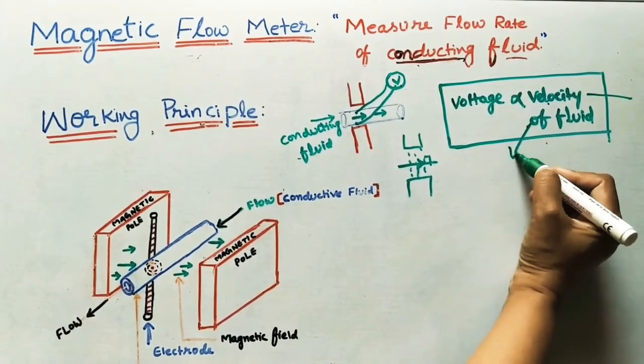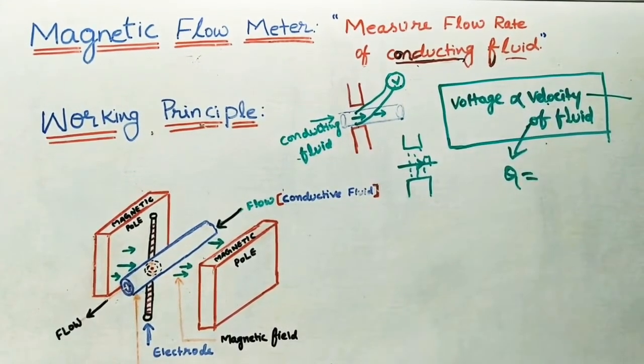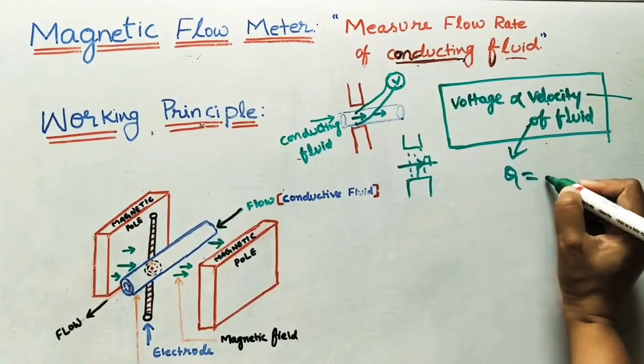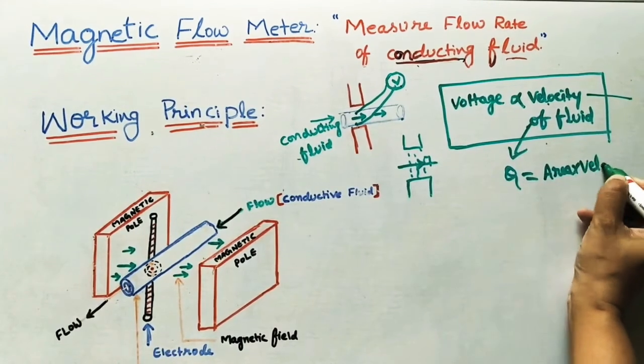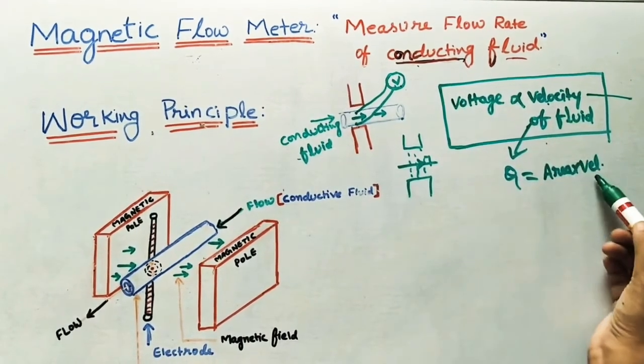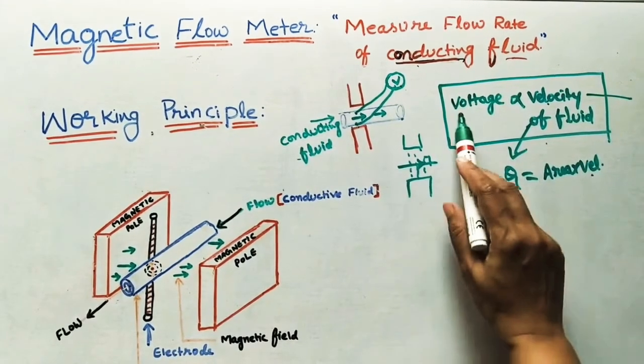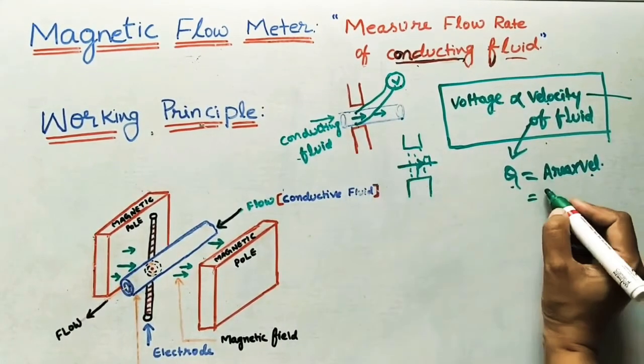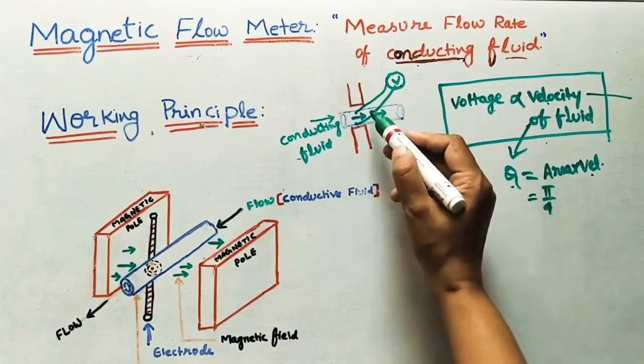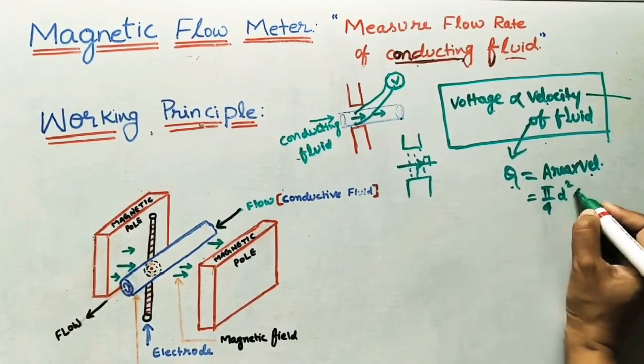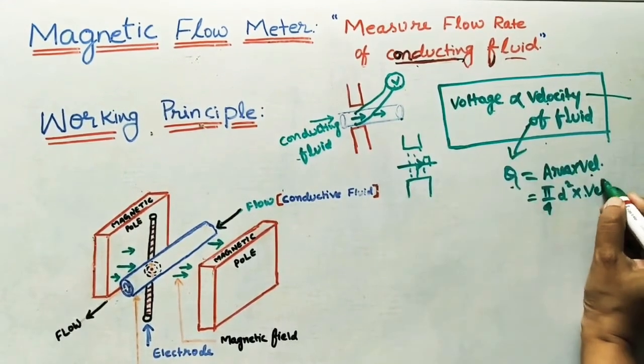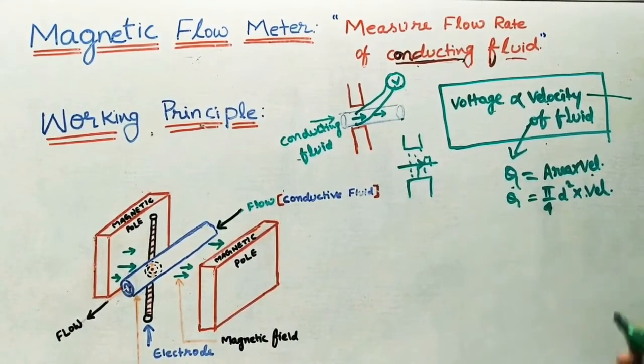Velocity gives voltage — but how do you find Q value? Q equals area of the pipe multiplied by velocity. For a circular pipe, area is pi/4 × D², so Q = (pi/4) × D² × velocity. The velocity is obtained from the voltage reading, and using a calibrated scale, the voltmeter reading is converted to give the discharge Q value directly. This is the main working principle.